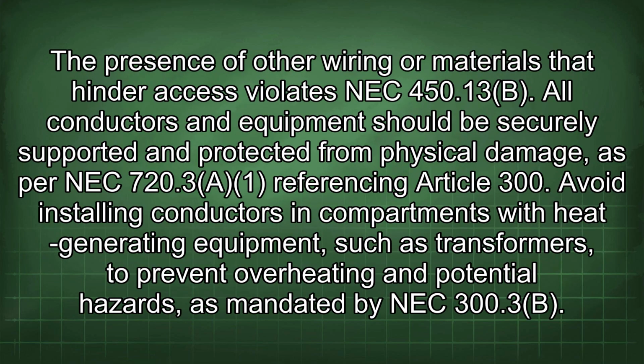The presence of other wiring or materials that hinder access violates NEC 450.13b. All conductors and equipment should be securely supported and protected from physical damage, as per NEC 720.3(A)(1) referencing Article 300.